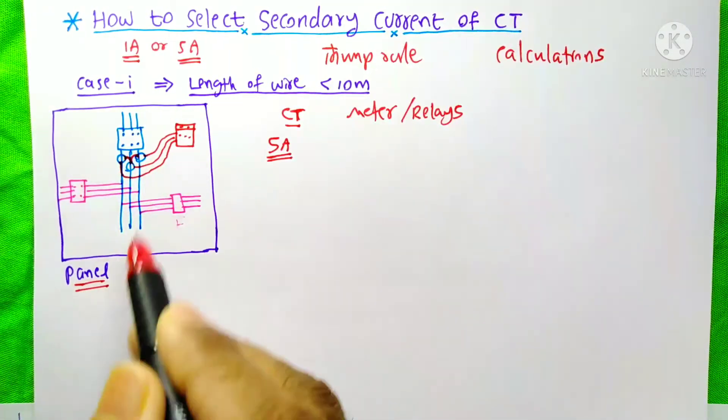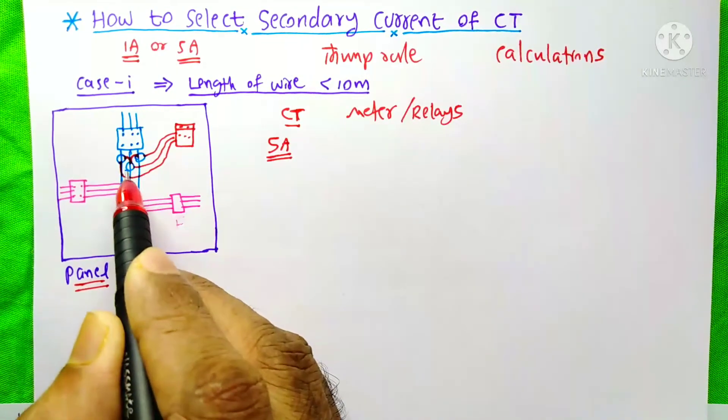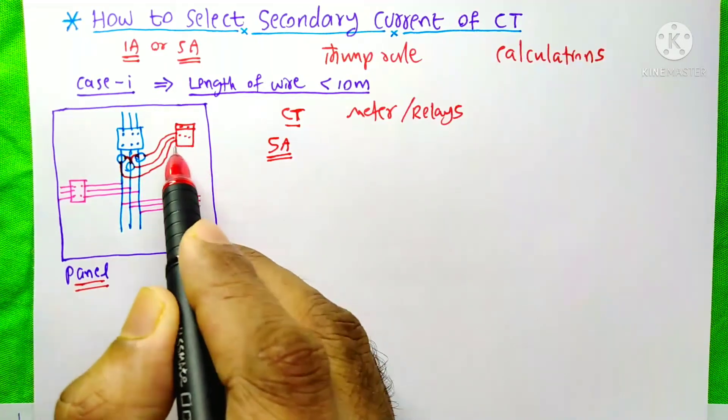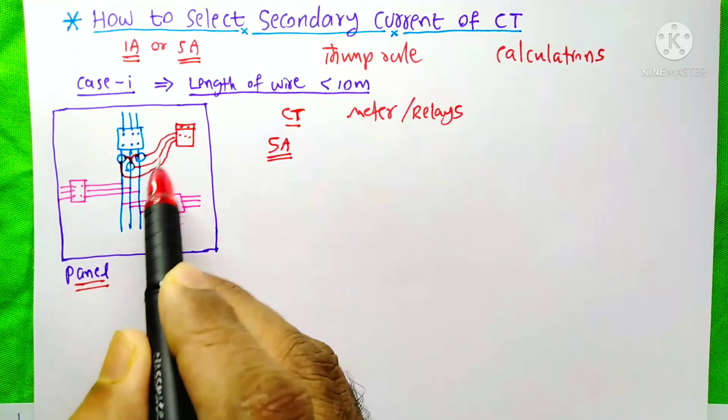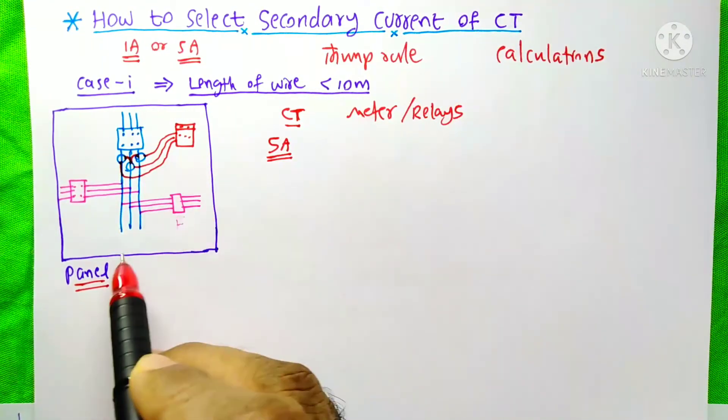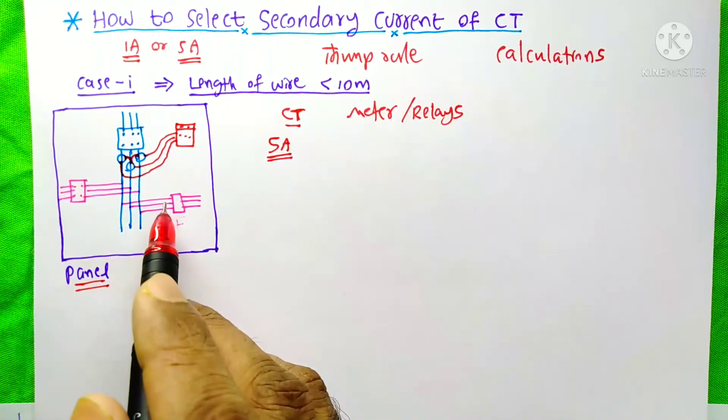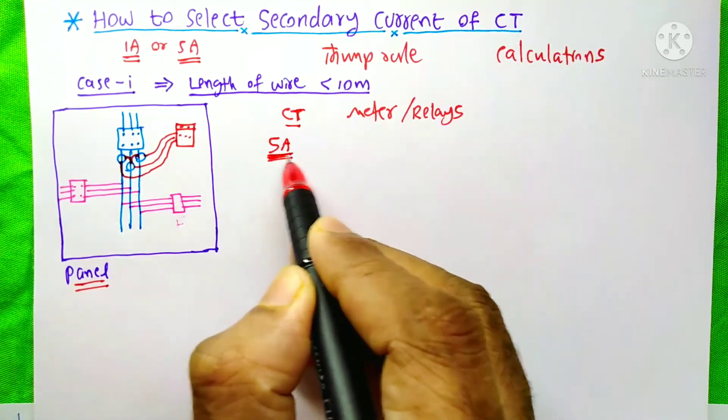In this case, we have an electrical panel and these are the CTs. Their secondary wires are connected to the meter or relay. In this case, the length of the wire is less than 10 meters because both are on the same panel. So we will use a CT with 5A secondary current.